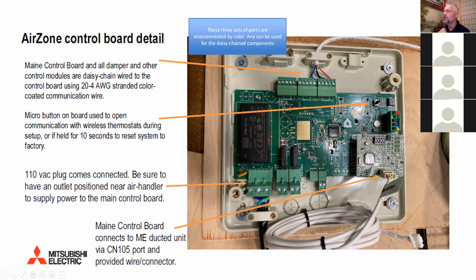There are a couple of auxiliary stages right here, but those are really just auxiliary backup, like if the whole system was experiencing a droop, you'd use those. But if you're using an air handler, you could just use the CN24 relays off of the air handler in order to activate hydronic heat or something else.